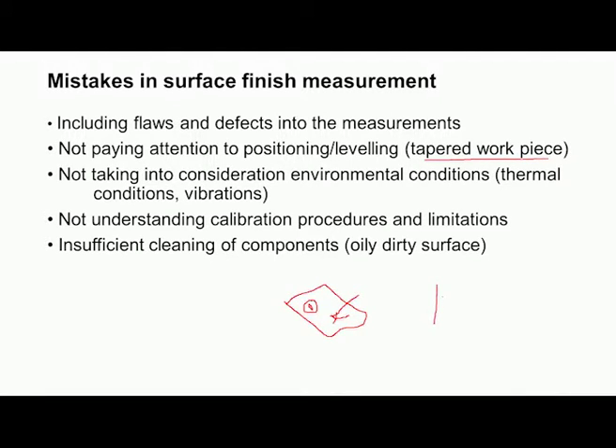For example, say we have a workpiece like this, and this surface finish we want to measure. Now if we allow the stylus to move like this, then instead of measuring the surface finish, it will measure the taper. So what we have to do is properly align and position the tapered workpiece like this, so that the surface is parallel to the movement of the stylus. For that, various fixtures and work holding devices are available, and we should use them, and properly position and level.